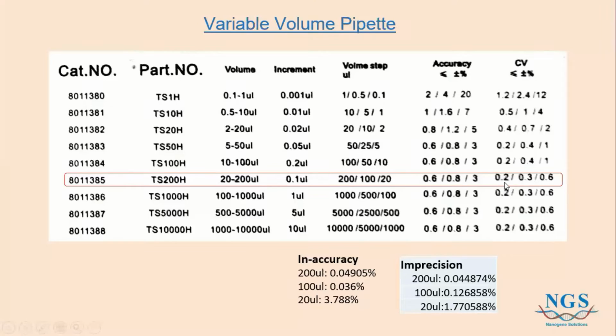All right, so let's say I have the results already. I did my 10 pipettings for each testing volume, I calculated my accuracy and precision, and these are the results that I got. You can refer to the results below. I have 3 inaccuracy values and 3 imprecision values, so in total, I have 6 values. So how do I know if these values are within the range, and how do I evaluate them? Let's take a look at inaccuracy. I'm looking at 200 microliters.